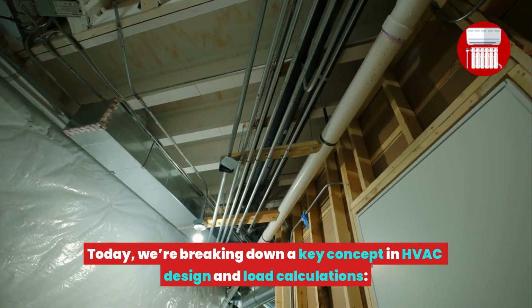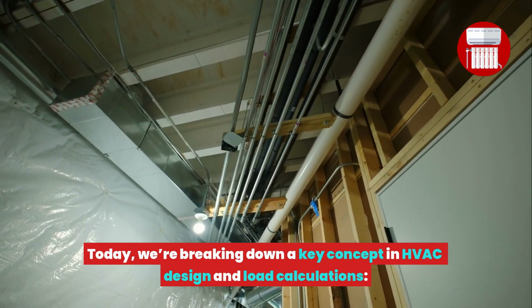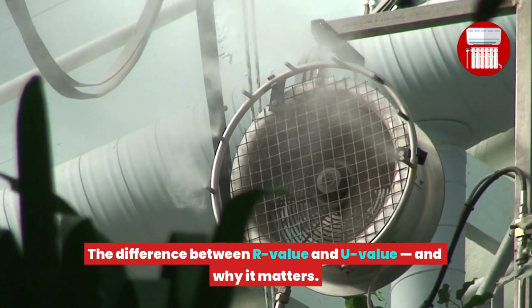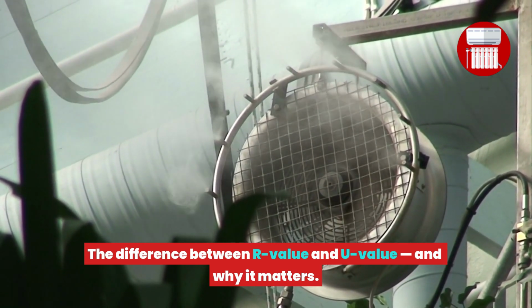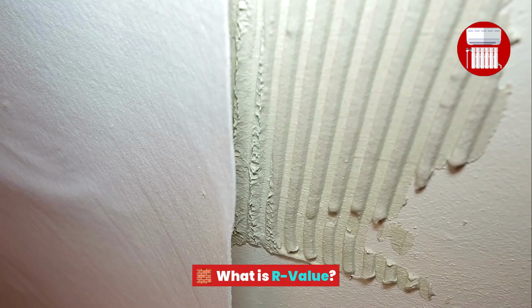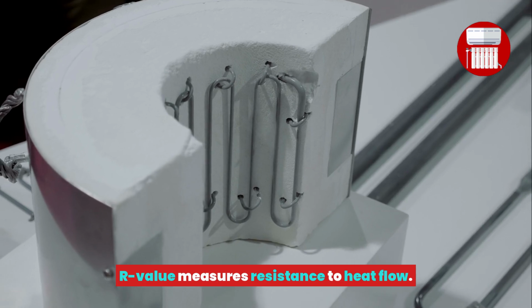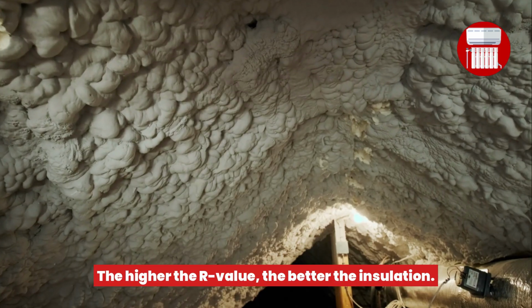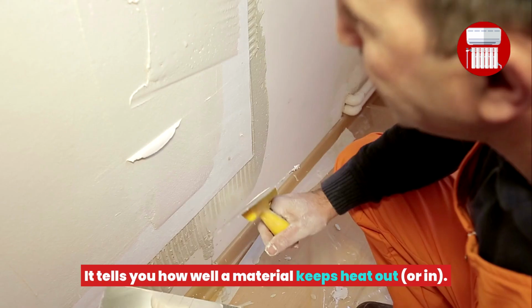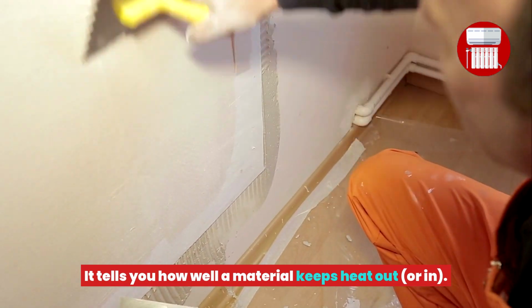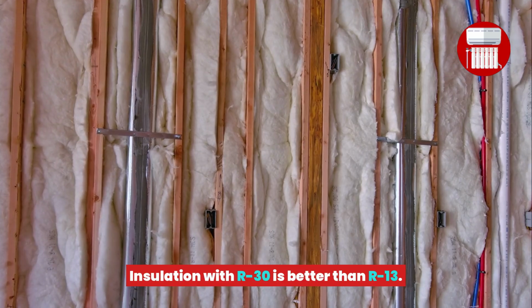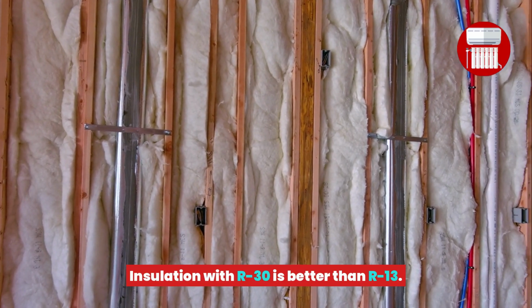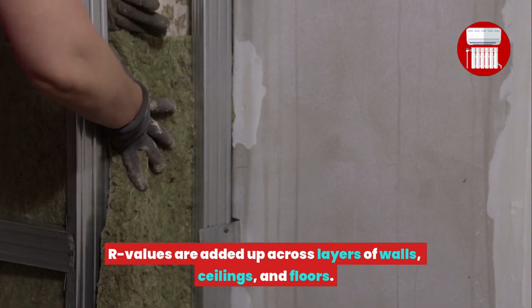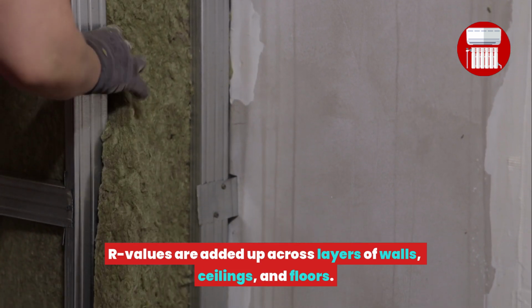Today we're breaking down a key concept in HVAC design and load calculations, the difference between R value and U value, and why it matters. What is R value? R value measures resistance to heat flow. The higher the R value, the better the insulation. It tells you how well a material keeps heat out or in. Example, insulation with R30 is better than R13. R values are added up across layers of walls, ceilings, and floors.